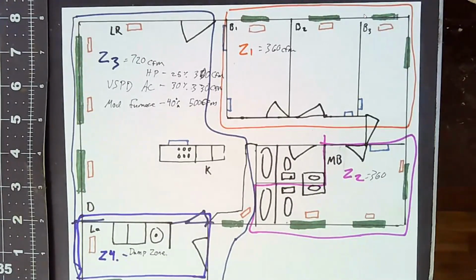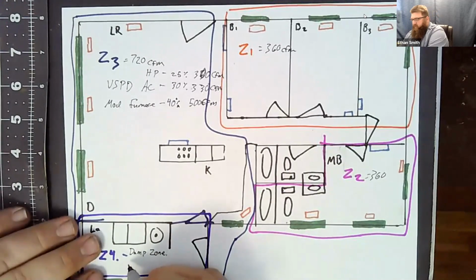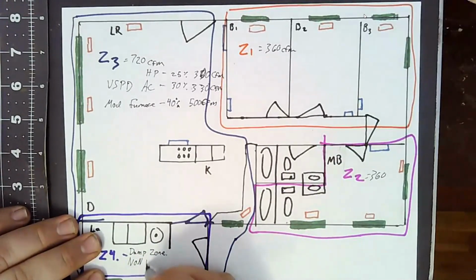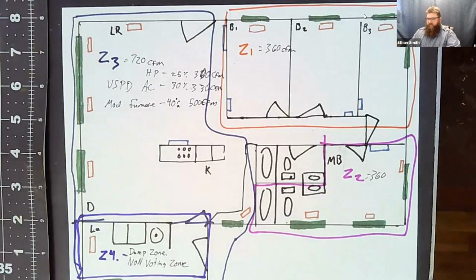Now there is a different type of dump zone that makes it intelligent. This is what we call a non-voting zone. That's what I was talking about. That's what I read about. Okay, so we've got to have a pretty smart zoning system to let us do non-voting zones. But basically, non-voting zones will take advantage of any excess air that's available, but they don't have the ability to turn the equipment on. So if I've got a call for heat and zone 2 turns the equipment on and gives me some heating capacity and I've got some excess air, it'll open up zone 4 and say, give me all that excess air until it hits set point. And then it will close that zone back down. Then we're going to have to do something else with the excess air at that point.